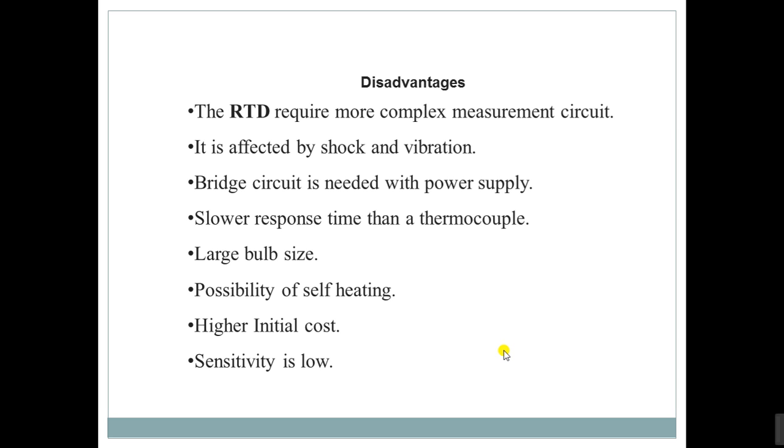The disadvantages are it requires a more complex measurement circuit, it is affected by shock and vibration. Compulsorily a bridge circuit is needed with a power supply to measure the resistance of the RTD device. Slower response time than thermocouple device, it has a large bulb size. Possibility of self-heating, due to the self-heating also some error will come, and the initial cost is very high and sensitivity is a little bit low.